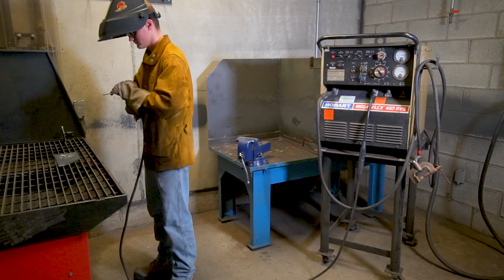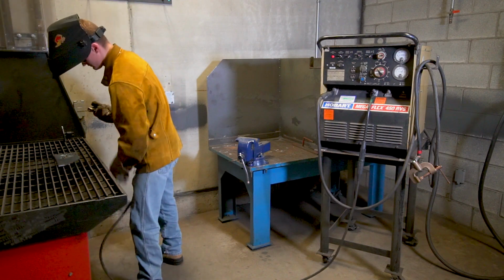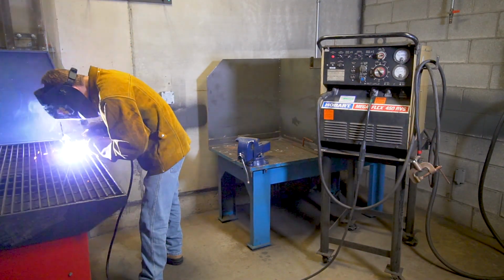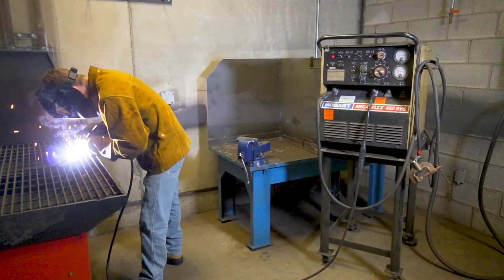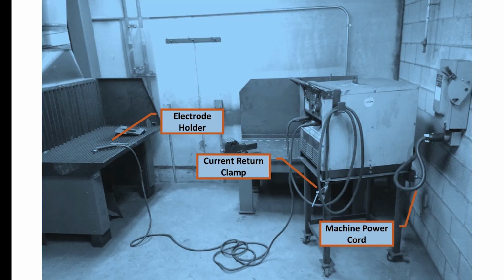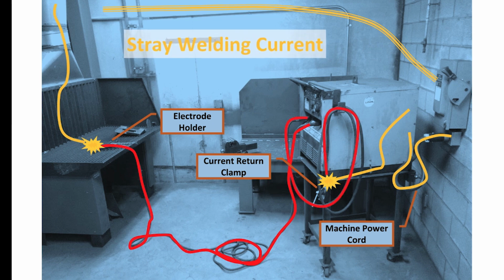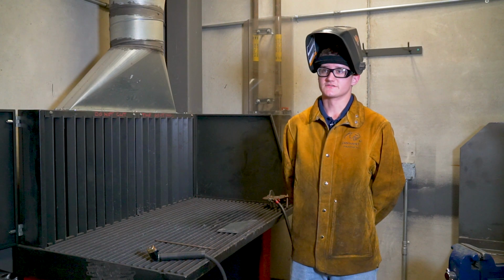It is important to realize that the overcurrent protection devices in the electrical system do not react in any way to this stray current fault condition. Remember that the machine that we are using could easily be welding or carbon arc gouging at over 450 amps in the same scenario and for much longer cycles.